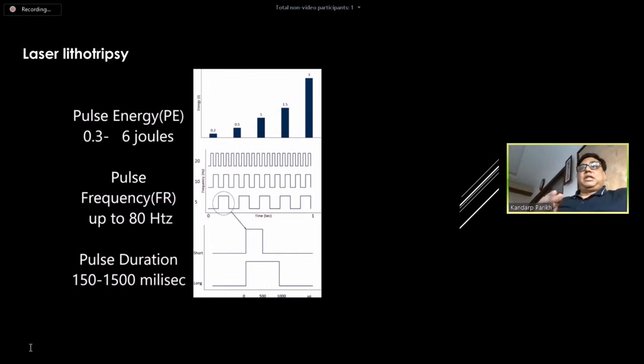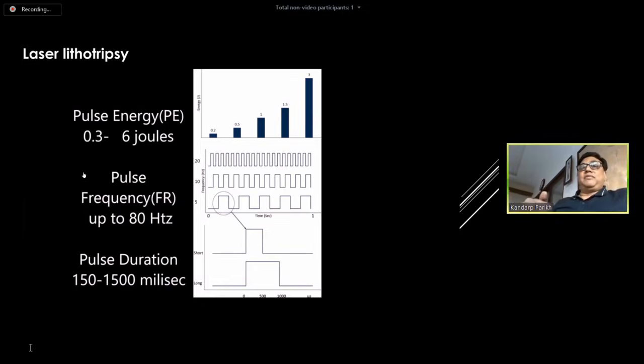If you decrease the energy, it produces good dusting. So it all depends on what's your philosophy, what is the size of the stone, what is the density of the stone, what you want to achieve, and the location of the stone. If you want to achieve a good dusting, you have to decrease the energy setting and keep it to 0.3, 0.4, 0.5 max. Similarly, pulse frequency is the number of pulses delivered in 1 second. In a low power laser, you can have up to 20 frequency, but in a high power laser, you can exceed the frequency to 80. The major advantage of this frequency is that it will speed up the procedure.